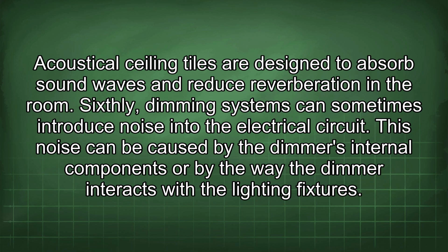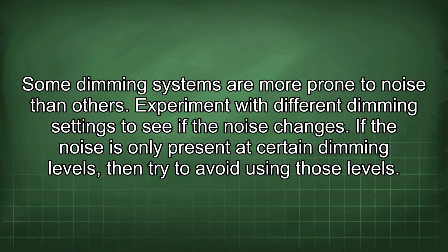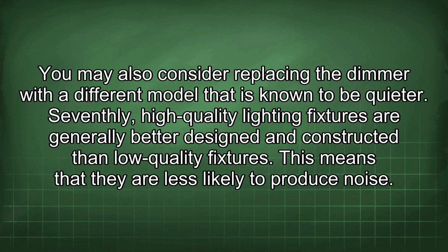Sixthly, dimming systems can sometimes introduce noise into the electrical circuit. This noise can be caused by the dimmer's internal components or by the way the dimmer interacts with the lighting fixtures. Some dimming systems are more prone to noise than others. Experiment with different dimming settings to see if the noise changes. If the noise is only present at certain dimming levels, then try to avoid using those levels. You may also consider replacing the dimmer with a different model that is known to be quieter.